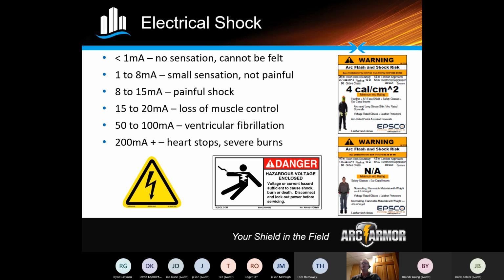And that's why there's been a huge push lately on short circuit and arc flash analysis. Doing those falls into the realm of developing what they call PPE, your personal protection equipment. We've been hearing a lot about that with the doctors and nurses on the whole virus situation, but we also have PPE requirements for panels. Those are all generated based on short circuit and fault studies that are done by third parties more times than not.